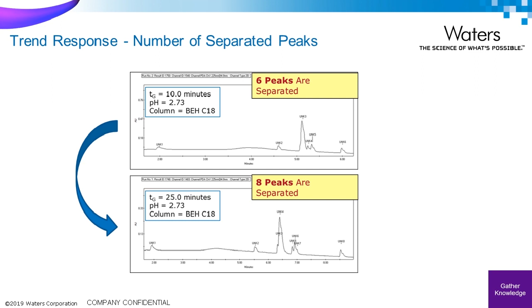Anything available there can be pulled in, so you can pull in things like tailing, peak height, etc. And we also automatically identify those things, so we do a peak count on the number of peaks well resolved, and we identify the max peak by the area response as well. So we can automatically calculate the resolution of the max peak, which might be your API.